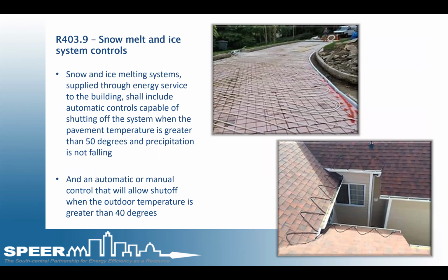403.9, snow and ice melt controls. We don't normally see these in Texas, but sometimes in Oklahoma and maybe in the hill country around Austin. These are not only used in flat work such as walkways and driveways, but can also include roofing systems that prevent damming that can lead to serious problems within the structure. These systems must have automatic controls capable of shutting off the system when the pavement temperature is greater than 50 and precipitation is not falling, like in flat work, driveways, and walkways. They must also have an automatic or manual control that allows for a shutoff when the outdoor temperature is greater than 40, like when used on roofing.